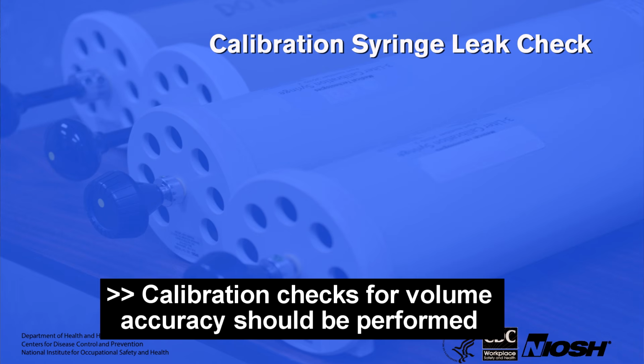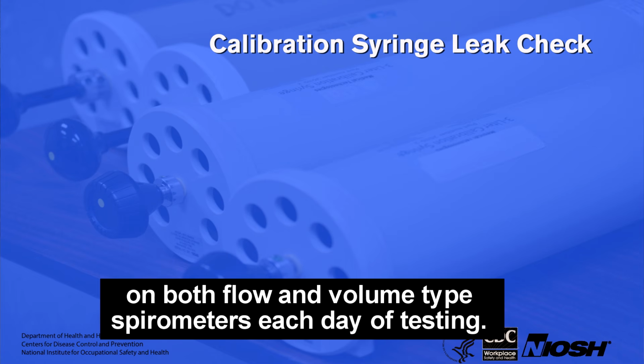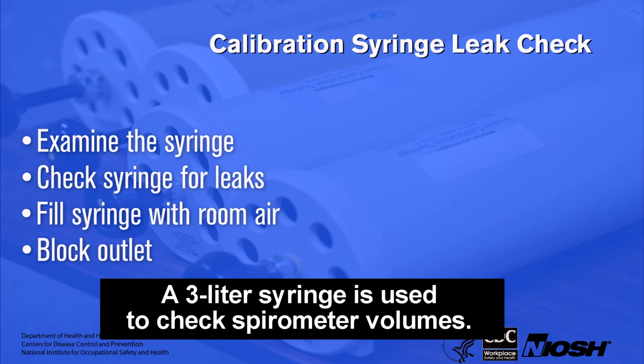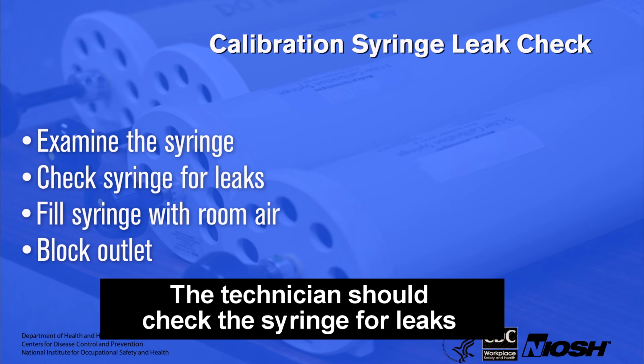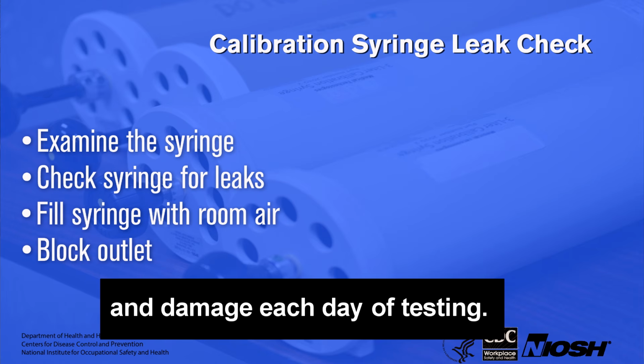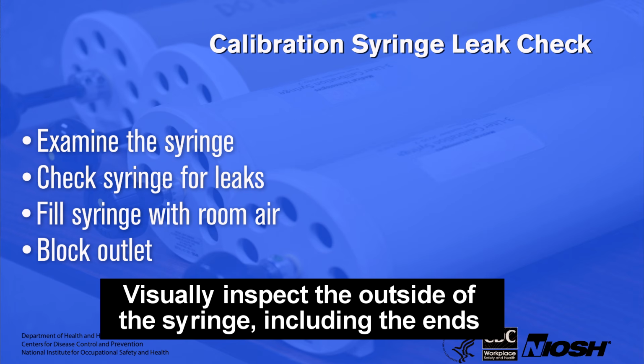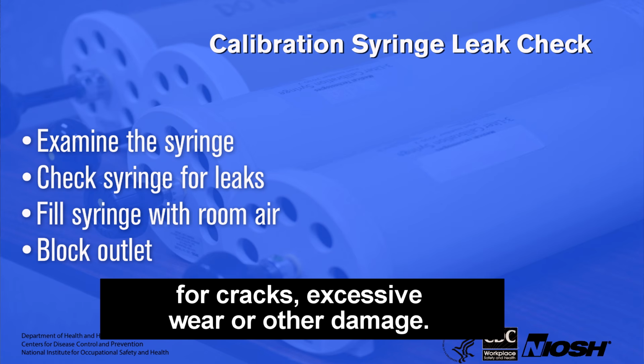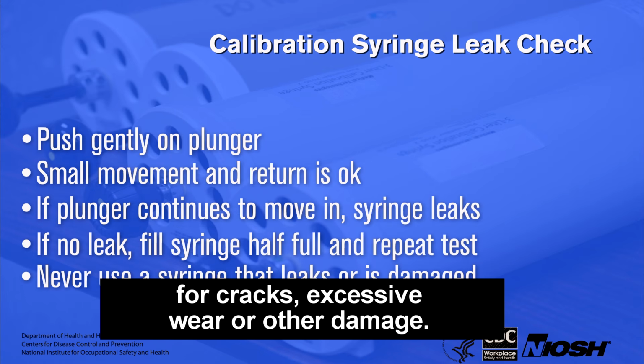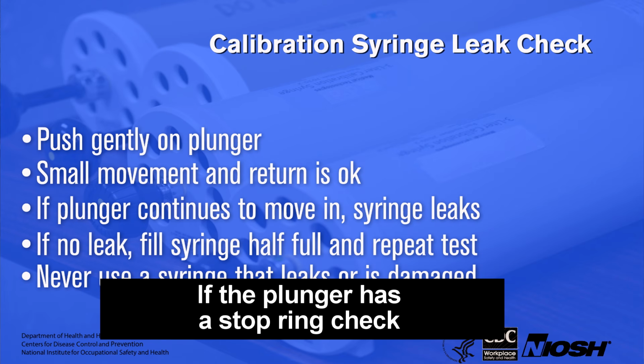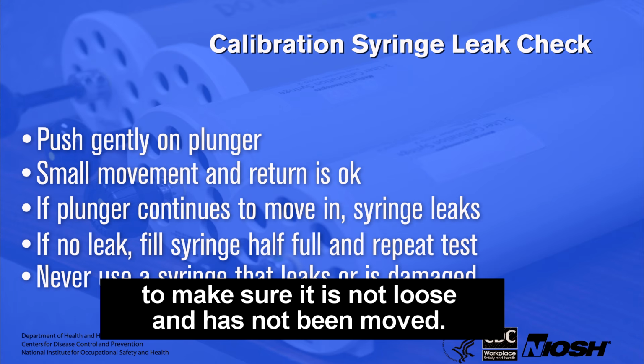Calibration checks for volume accuracy should be performed on both flow and volume type spirometers each day of testing. A 3-liter syringe is used to check spirometer volumes. The technician should check the syringe for leaks and damage each day of testing. Visually inspect the outside of the syringe, including the ends, for cracks, excessive wear, or other damage. If the plunger has a stop ring, check to make sure it is not loose and has not been moved.